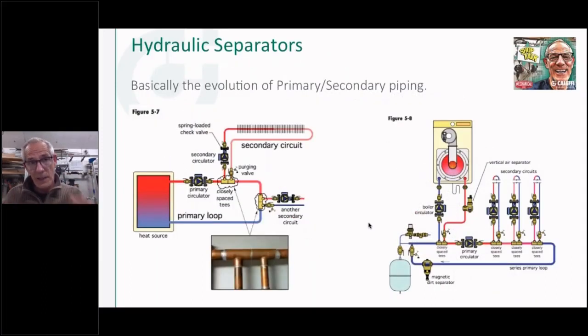So we talked about this, I know, on the last one, but let's just review it a little bit for those that are just tuning in. So the concept came out of the Bell and Gossett folks, and they said, you know what, if you put a couple of T's together and you put them close enough, and you had this pipe here sized, let's call this the primary loop, large enough to accommodate the flow going through this loop through the boiler, and these T's are close enough together, very little pressure drop when you have two T's closely spaced like that.